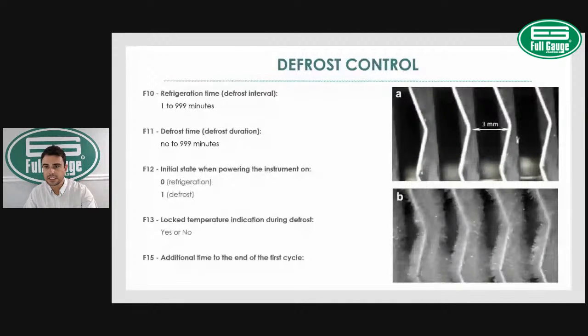So what are the other defrost parameters we have in here? The other defrost parameter is F12, the initial state when powering the instrument on. What that means is that I can set the controller to start on refrigeration or to start on a defrost cycle. Why would I set the controller to start on a defrost cycle? Does anyone know why we have that option?